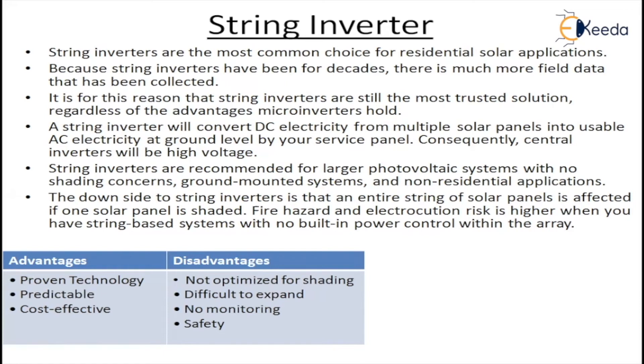The downside of the string inverter is that if one solar panel is shaded, the entire string of solar panels is affected. Fire hazard and safety risk are higher in a string-based system with no built-in power control within the array. Advantages: mature technology, predictable and cost-effective. Disadvantages: not optimized for shading, difficult to expand, no monitoring, no safety point, and fire hazards are a problem.